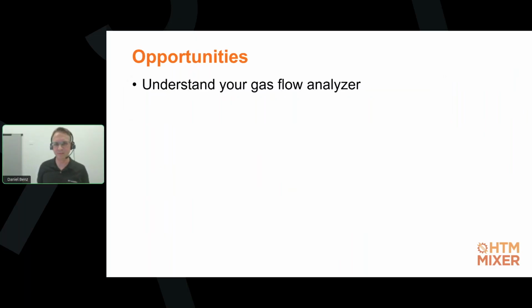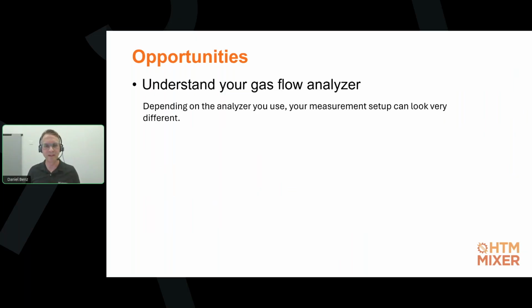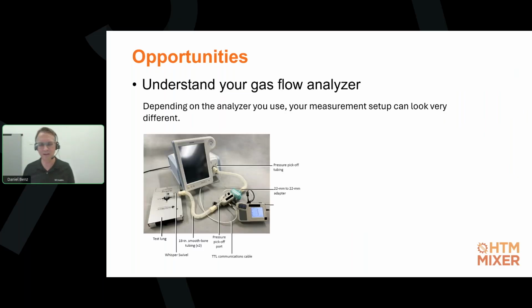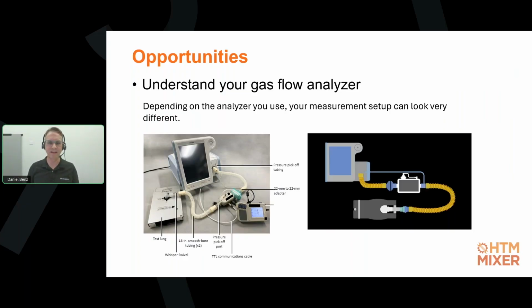Of course, we can't expect the ventilator manufacturers to add pictures for each and every analyzer available in the market, and they also wouldn't do that, right? Therefore, it is crucial for you to understand your gas flow analyzer, because depending on the analyzer you use, your measurement setup can look very different. For example, the setup we see in the picture here on the left-hand side of the screen, which we saw a little earlier, can look as simple as in the picture on the right side for a different analyzer.